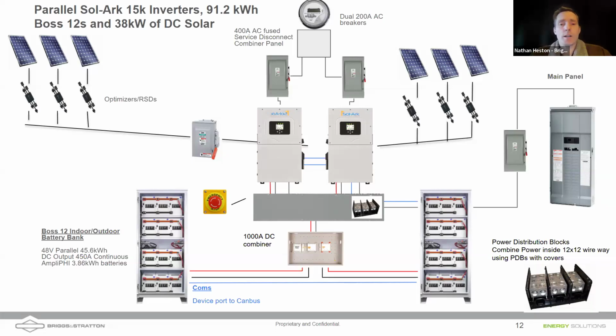And we're also looking at a DC combiner here. I like this because it's important to know anytime you parallel inverters, you have to use a combiner for your batteries. You cannot bring one battery stack into one inverter and a different battery stack into the other inverter. They have to be operating at the same voltage.